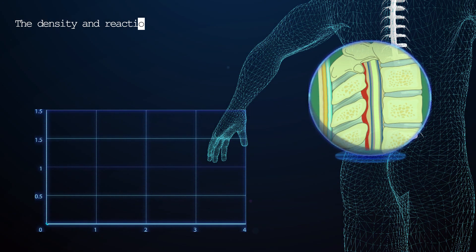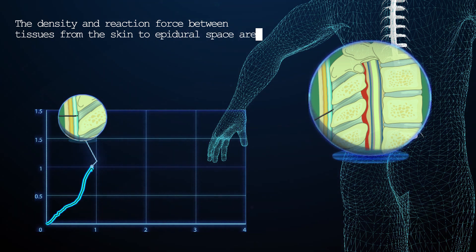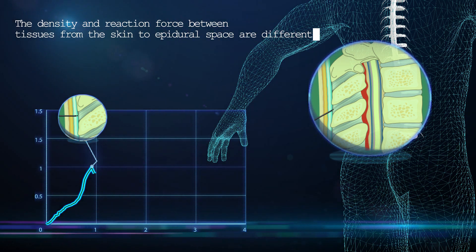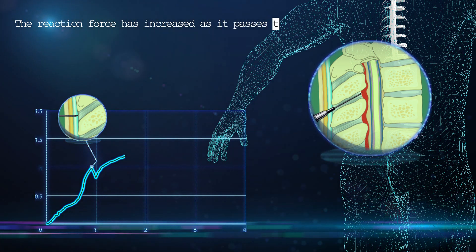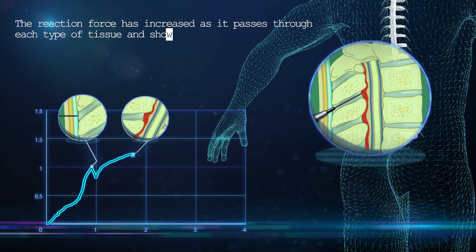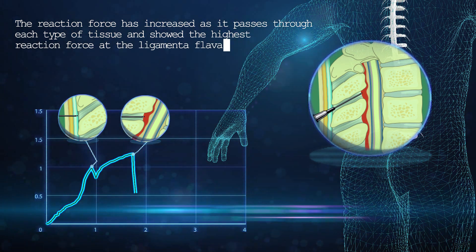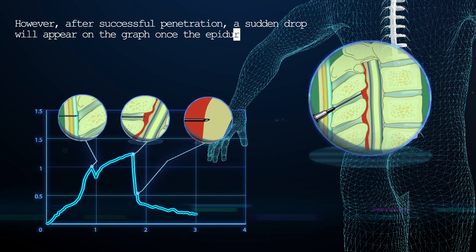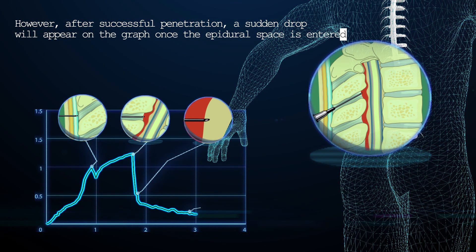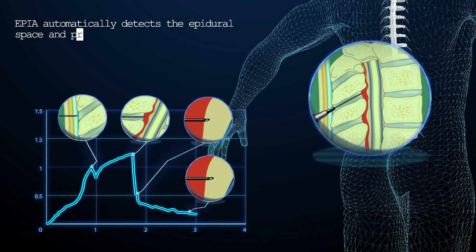The density and reaction force between tissues from the skin to the epidural space are different. The reaction force increases as it passes through each type of tissue and shows the highest reaction force at the ligamenta flava. However, after successful penetration, a sudden drop will appear on the graph once the epidural space is entered. EPIA automatically detects the epidural space and provides a safe drug injection.